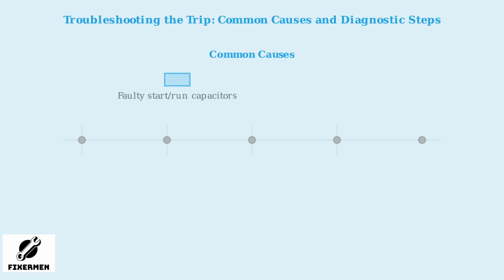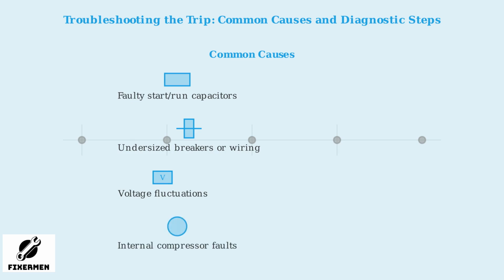Several factors can contribute to inrush current tripping in Lennox AC units. These include faulty start or run capacitors, which provide the initial electrical boost needed for startup. Undersized breakers or wiring, such as using 10-gauge wire instead of the recommended 8-gauge, can also cause tripping by not handling the surge properly. Voltage fluctuations, where the electrical supply drops below the required level, often exacerbate the problem. Internal compressor faults, like worn bearings or other mechanical issues, can lead to excessive current draw during startup.